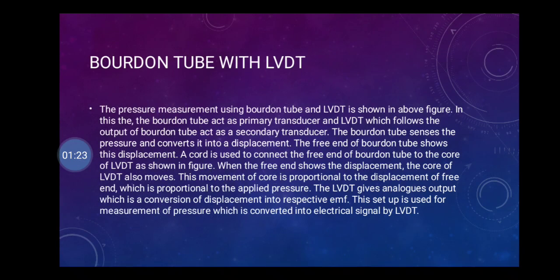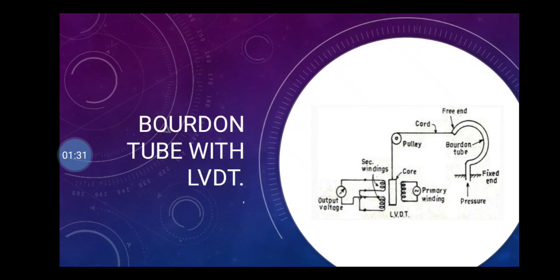The pressure measurement system contains the main components: C-type Bourdon tube, single pulley arrangement, LVDT construction, magnetic core, pressure gauge, primary winding, secondary winding, pulley. A primary transducer, here a C-type Bourdon tube manometer, is a detector which senses the physical phenomenon. A C-type Bourdon tube comes in contact with the pressure which is to be measured. This converts the pressure into a proportional displacement at its free end.